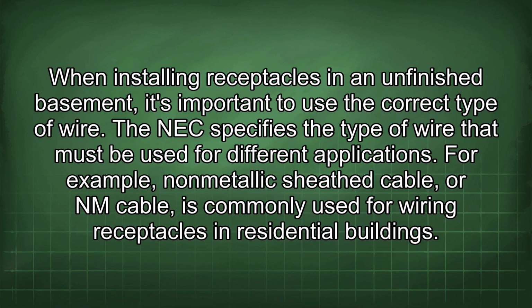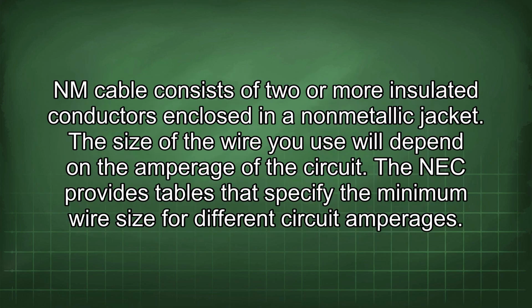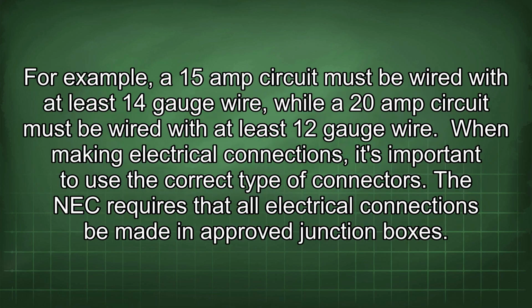The NEC specifies the type of wire that must be used for different applications. For example, non-metallic sheath cable, or NM cable, is commonly used for wiring receptacles in residential buildings. NM cable consists of 2 or more insulated conductors enclosed in a non-metallic jacket. The size of the wire you use will depend on the amperage of the circuit. The NEC provides tables that specify the minimum wire size for different circuit amperages. For example, a 15 amp circuit must be wired with at least 14 gauge wire, while a 20 amp circuit must be wired with at least 12 gauge wire.